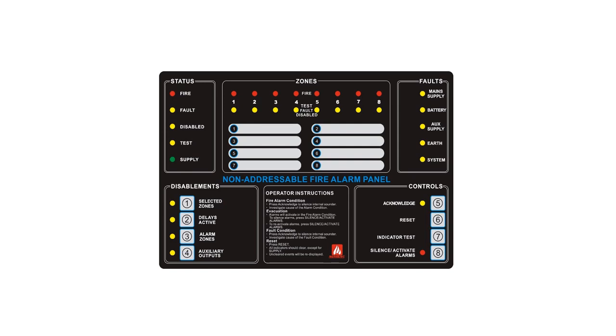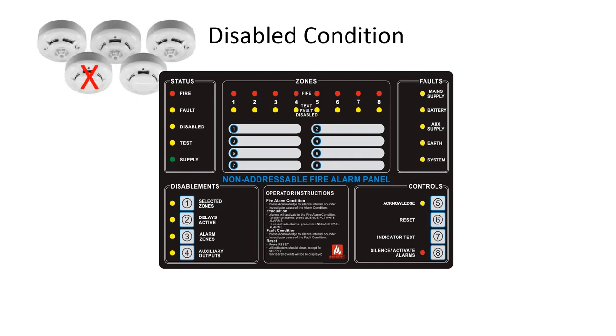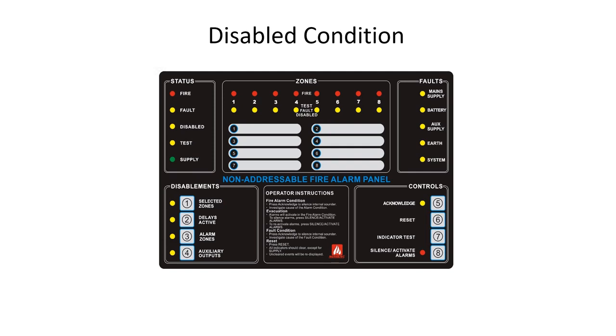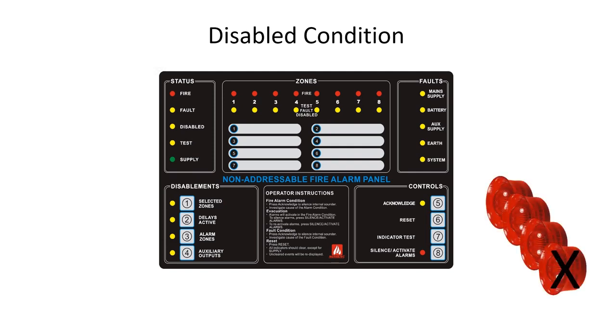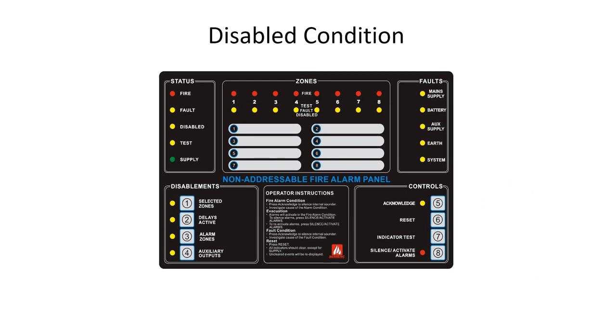A function may be manually disabled, the disabled condition. This prevents events from within the zone, such as a detector alarm, from being actioned by the control panel, from actions initiated by the control panel, such as the activation of an audio-visual alarm device occurring within the zone, or from signals being sent to auxiliary outputs. In the disabled condition, the disabled status indicator will be on.